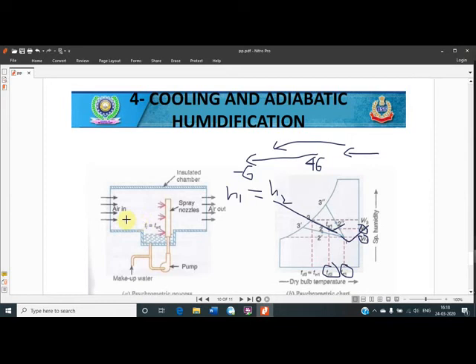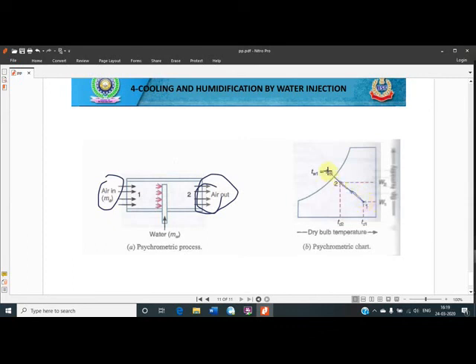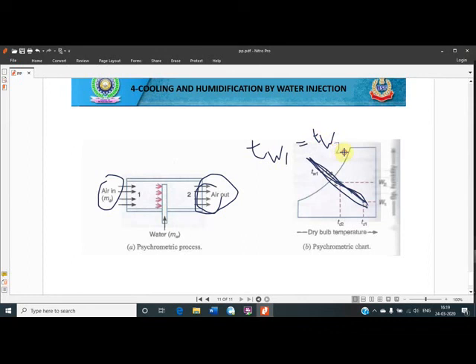The humidification process can be done in two ways. Either water is sprayed over the air, and by evaporation some water goes with the air, and make-up water is pumped again. Another process is cooling by water injection: instead of spraying, water is directly evaporated into the inlet air and the exit air gets humidified. This is shown by a particular inclined line. When we move along this inclined line, the wet bulb temperature at point 1 remains the same at point 2, because wet bulb temperature lines are inclined lines. The enthalpy at points 1 and 2 also remains the same.